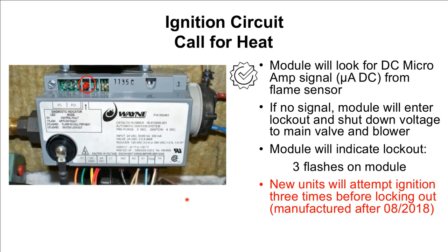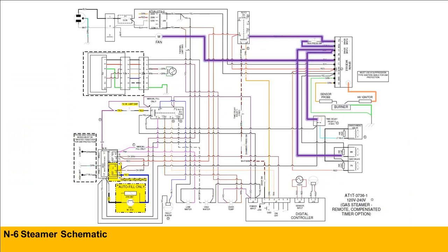So the blower will continuously run throughout this try. If it is unsuccessful, again, 3 flashes. And that module is backwards compatible. So if you are replacing an ignition module on a unit older than August of 2018, you will use the new 3-try module, and that is available from Partstown. I'm going to pass it back to Andy, and he's going to walk you through testing the ignition circuit.